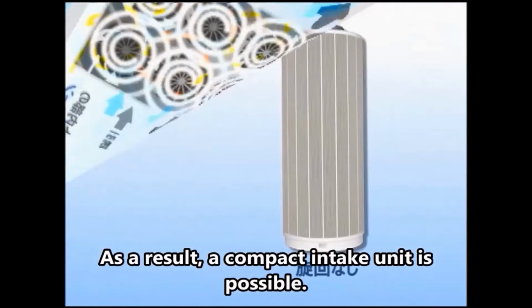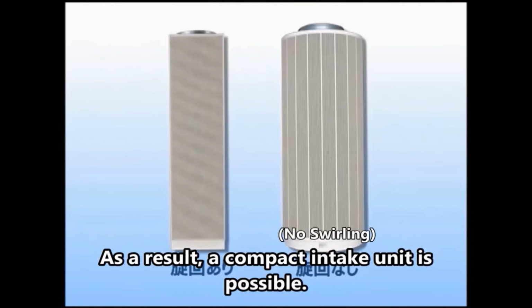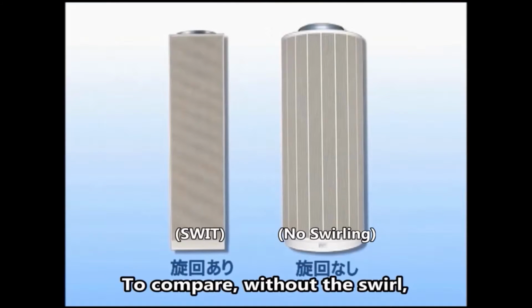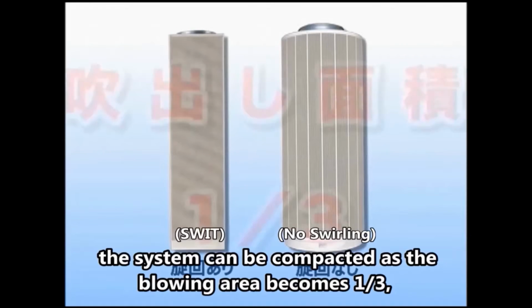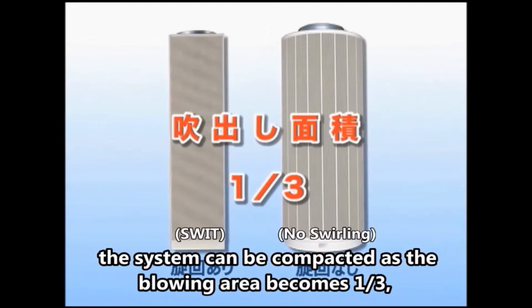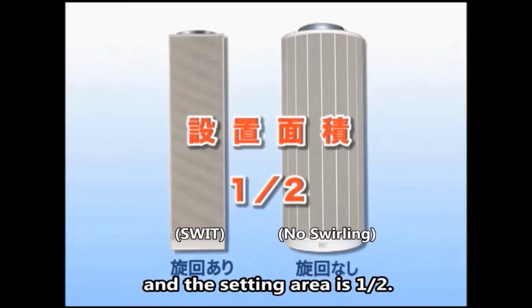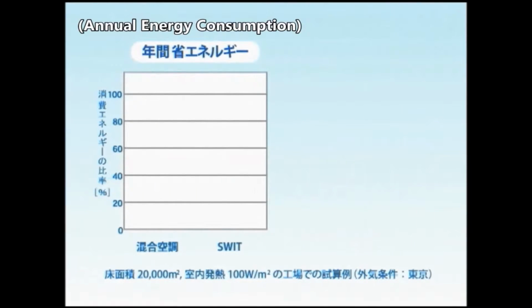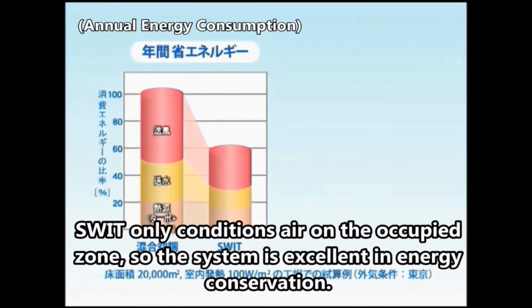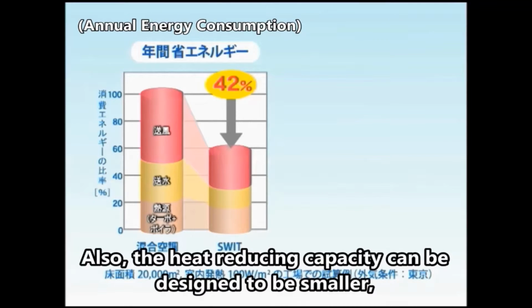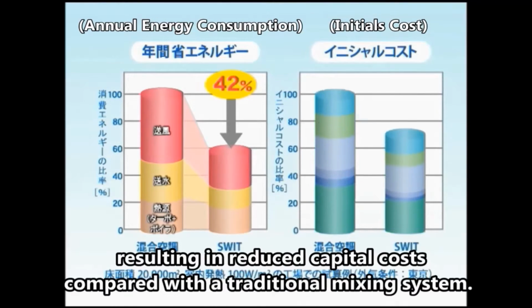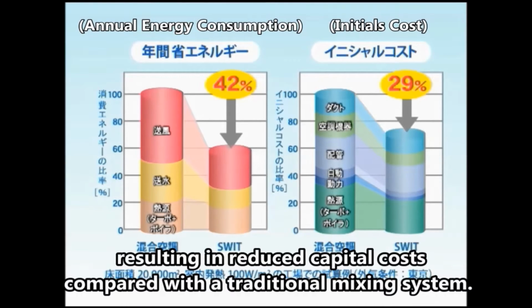As a result, a compact intake unit is possible compared to one without the swirl, as the blowing area becomes 1/3 and the setting area is half. Swit only conditions air in the occupied zone, so the system is excellent in energy conservation. Also, the heat-reducing capacity can be designed to be smaller, resulting in reduced capital costs compared with the traditional mixing system.